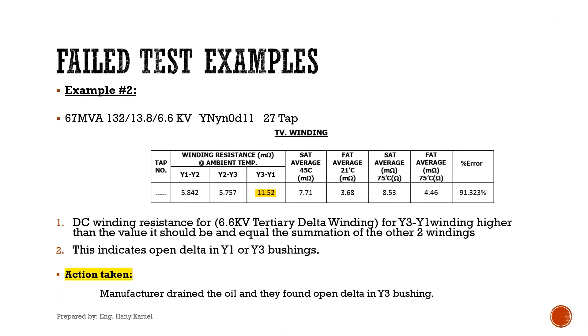Second example: a power transformer with 67 MVA, 132/13.8/6.6 kV, YNyN0D11 with 27 taps. The DC winding resistance for the 6.6 kV tertiary delta winding for the Y3–Y1 winding was higher than expected and equal to the summation of the other two windings. This indicates an open delta in the Y1 or Y3 bushings. The manufacturer drained the oil and found an open delta in the Y3 bushing.